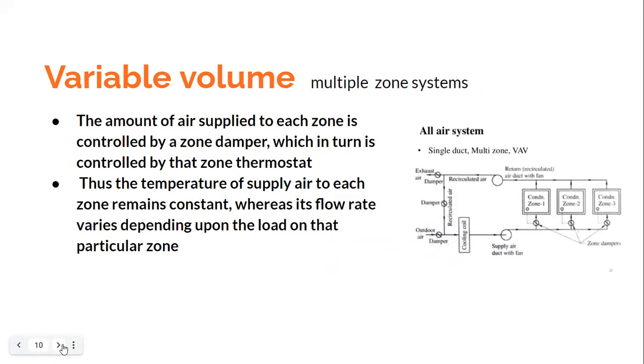Then, as I said, along with the constant volume, you might think of a system where the volume could be changed. If the volume could be changed, it becomes a variable volume system. The amount of air supplied to each zone is then controlled by a zone damper. So you see that there are zone dampers here. In this diagram, it is clear. The conditioned air is coming and different air flow rates go into the different zones. So in zone 1, you might have a flow rate Q1, in zone 2 a flow rate Q2, and in zone 3 a flow rate Q3. Different flow rates are possible by putting the dampers over here.